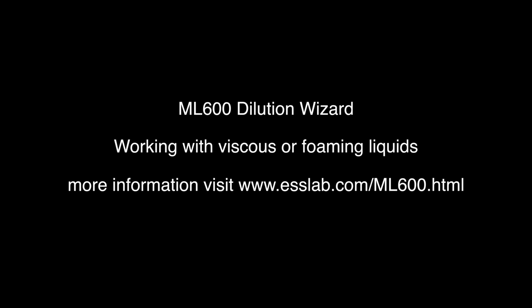Yeah, it's particularly relevant, Chris, when you're using biological samples. In many instances, things like serum, plasma or whole blood have difficulties when you're aspirating at higher speeds. So we have an option in the advanced functions here, and within the advanced functions, we have options for the fill, aspirate and dispense speeds.